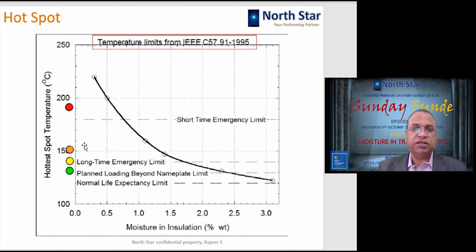This range is short time emergency loading, not continuous loading, but you can load it up to 200 degrees centigrade for a very short amount of time without affecting it. If your moisture is high, say it's 2%, then your hotspot is somewhere around 120 degrees centigrade only. Okay, so with moisture, the transformer's capability of bearing the load comes down.